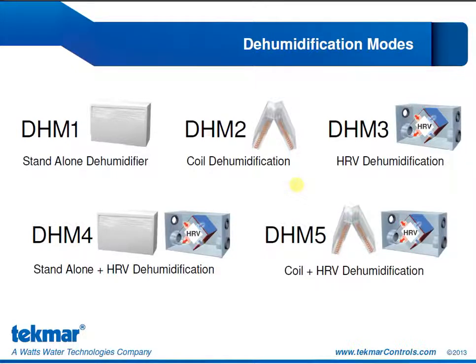Dehumidification mode 2 is for coil dehumidification. Now, in this case, air passes over the cold coil, and the water vapor condenses, and the outgoing air becomes cooler and drier. Clearly, this is not available during heating. We have to be cooling for this to be possible. And it does require a duct sensor to make sure we don't freeze our coils.